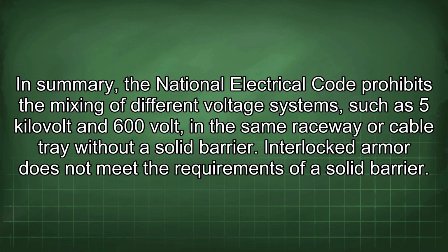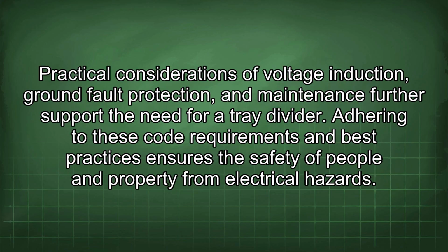In summary, the National Electrical Code prohibits the mixing of different voltage systems, such as 5 kV and 600 volt, in the same raceway or cable tray without a solid barrier. Interlocked armor does not meet the requirements of a solid barrier. Practical considerations of voltage induction, ground fault protection, and maintenance further support the need for a tray divider. Adhering to these code requirements and best practices ensures the safety of people and property from electrical hazards.